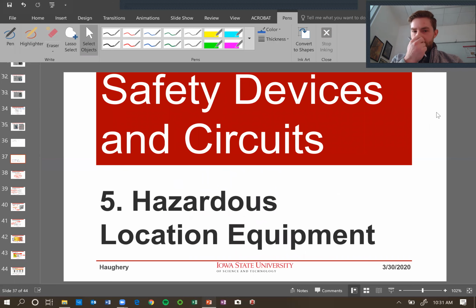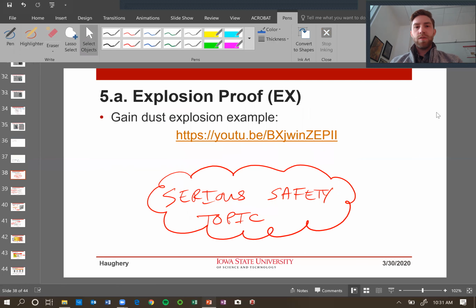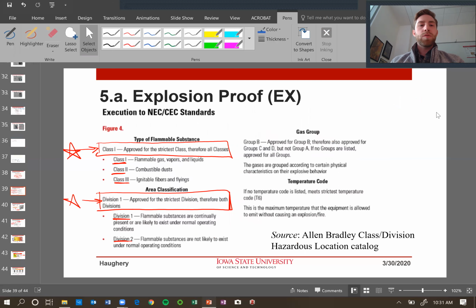And then hazardous location equipment. There's a couple things here to be considering. There are some videos that you could watch, pretty interesting grain dust explosion videos. But really we want to think about two different types, divisions and classes, of explosive environments. And so we have the class, which is class 1, 2, 3. That's where we're defining the flammable or combustible, ignitable things in the air that actually make that fire or explosion possible.